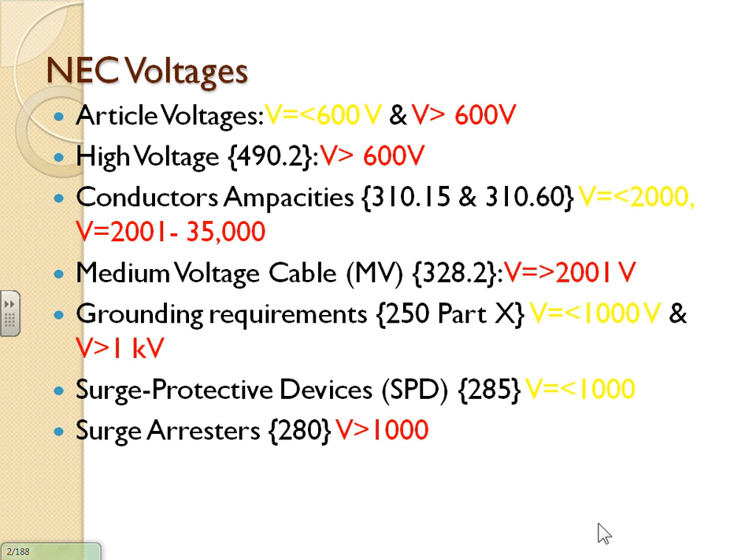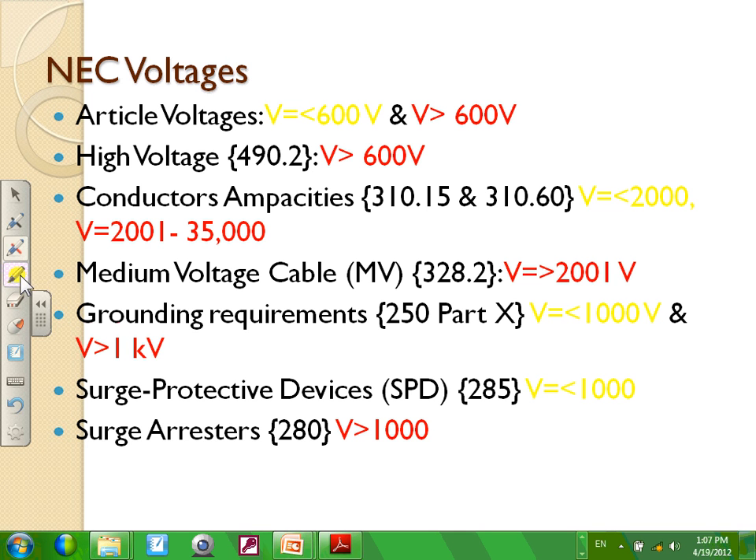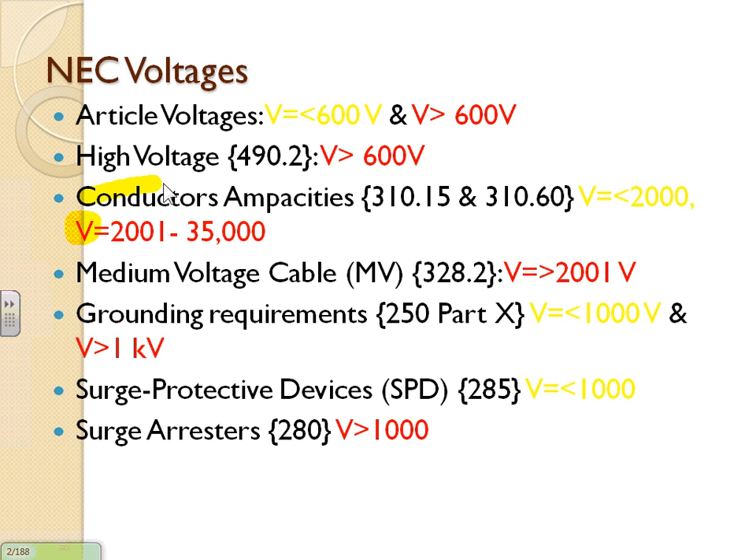Voltage-wise, the cutoff is 600V or less versus more than 600V. Conductor-wise, if you go to NEC 310.15(B)(16) — which used to be 310.16 — the table gives ampacities up to 2,000 volts. They divide conductors into 2,000 volts and below versus higher than 2,000 volts. So there's a voltage division for the system and a separate voltage division for the conductors.